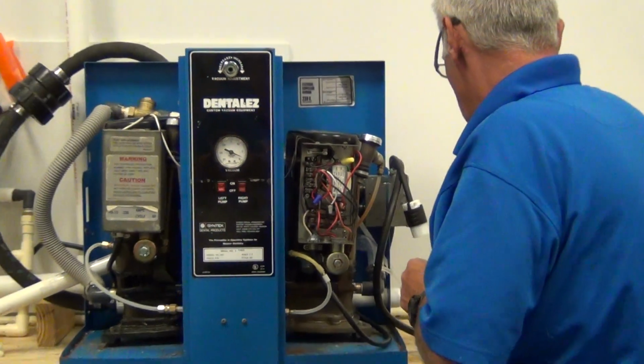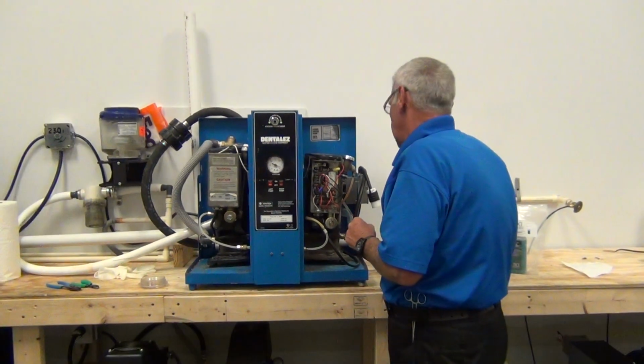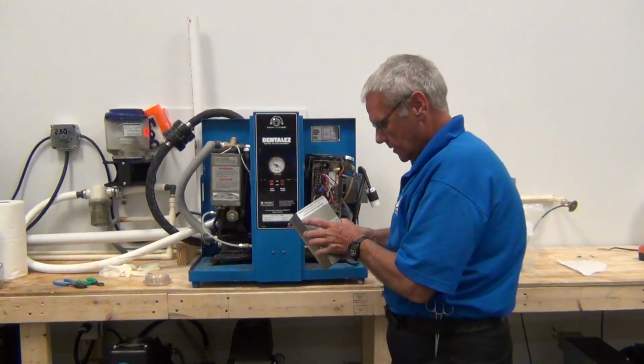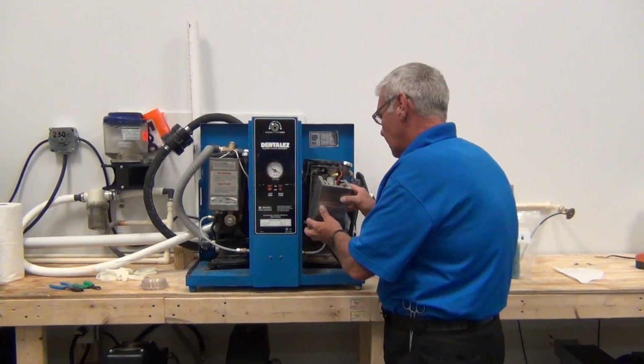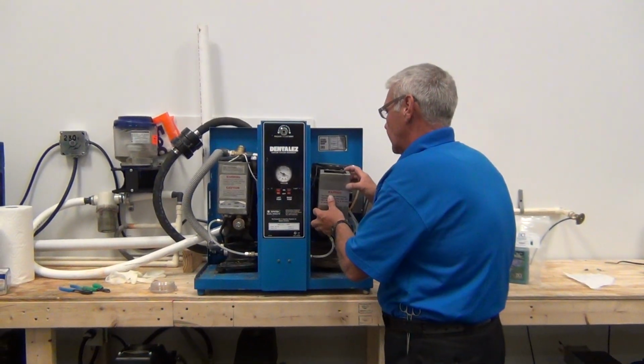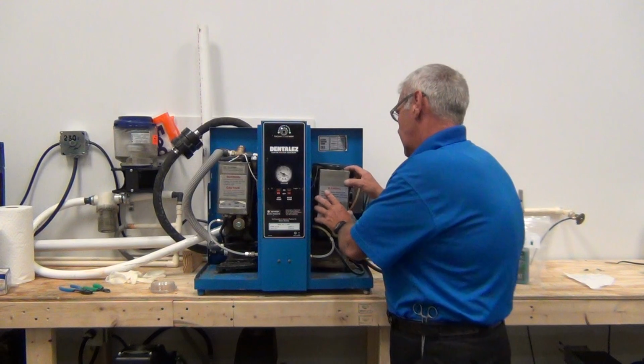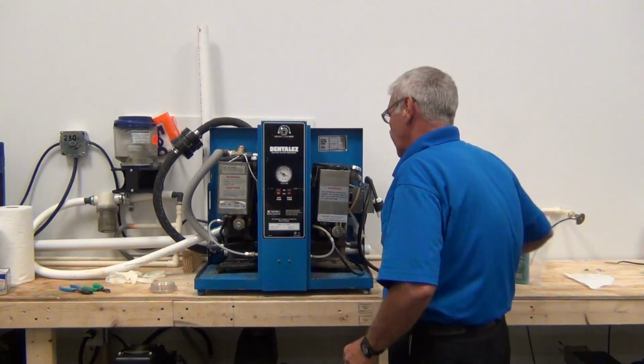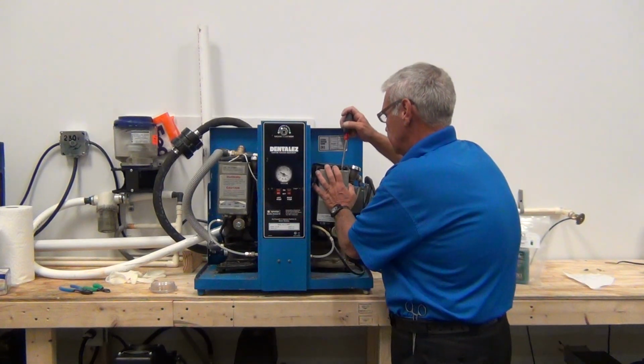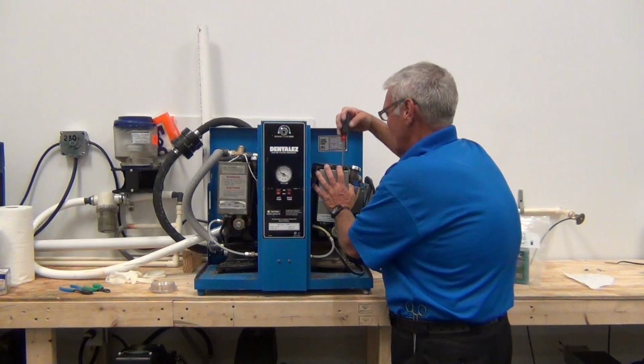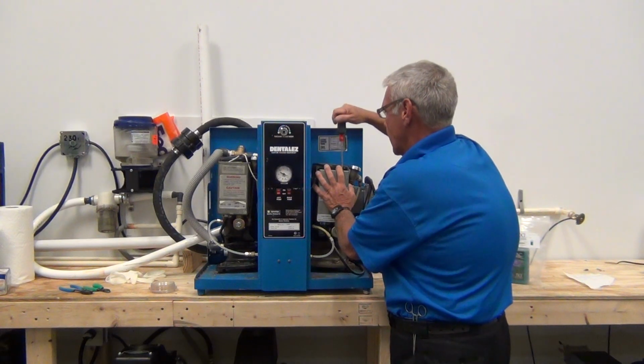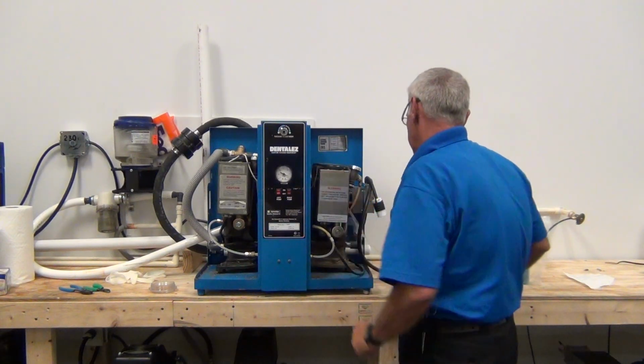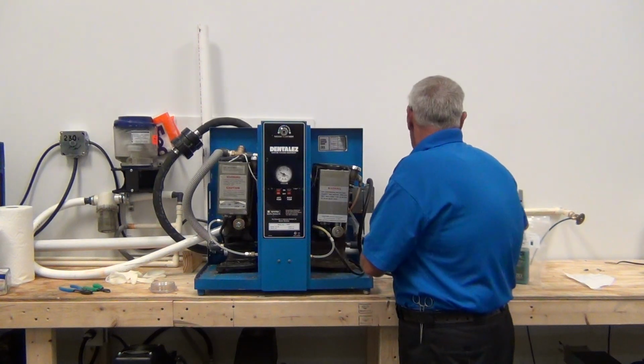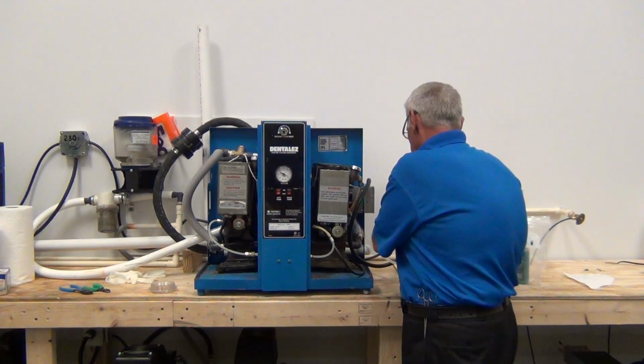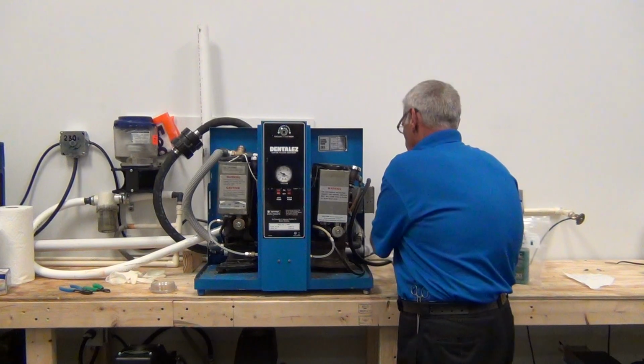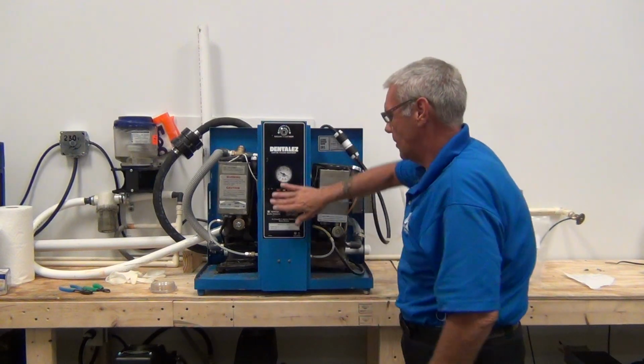Most of your maintenance issues with this pump are going to be a water leak. The tubings are not very durable on them, and you will need to replace tubings more often than anything else in this pump. This pump's been on the market for about 30 years now. One of the best. Restore your power. Turn the pump back on.